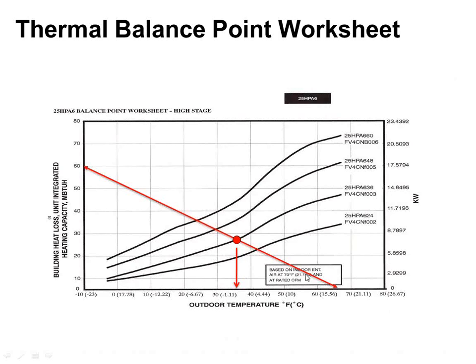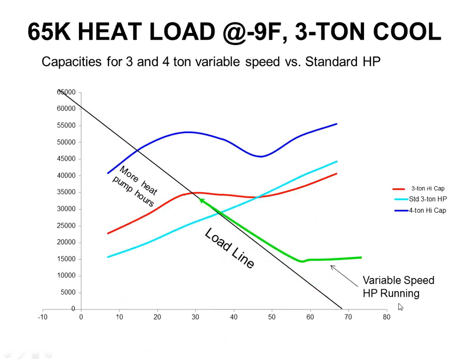Clear that drawing off too. All right, so this is how it might look, right? This is kind of a similar graph to the one I just showed you. This is more of what happens when I put a variable speed piece of equipment on here. This graph does also go from -10 on the left to 80 degrees on the right. Up the left-hand side, it goes from 0 to 65,000 BTUs. At 65,000 BTUs, it's a -9 degree day is where this guy kind of caps out over there.